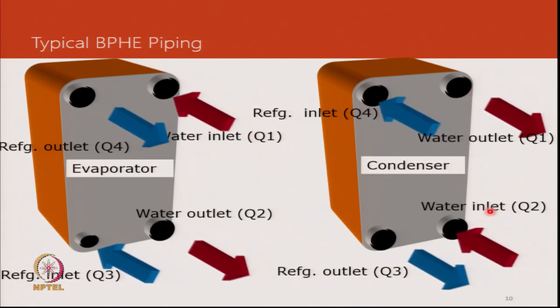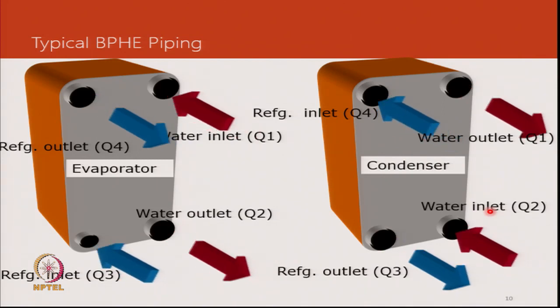Typical piping for a brazed plate heat exchanger differs between evaporator and condenser applications. In an evaporator, the refrigerant enters at the bottom and leaves on top to maximize the opportunity for refrigerant to evaporate and achieve the best heat transfer. Water enters on top and leaves at the bottom, and this is just reversed in the condenser.